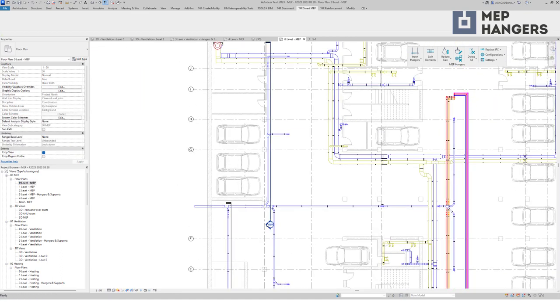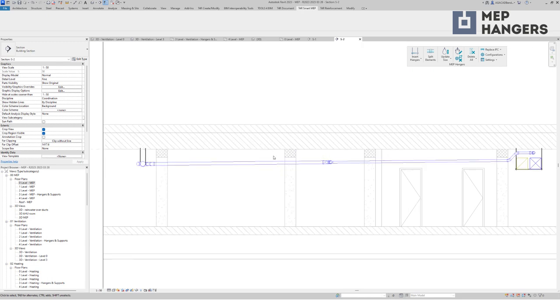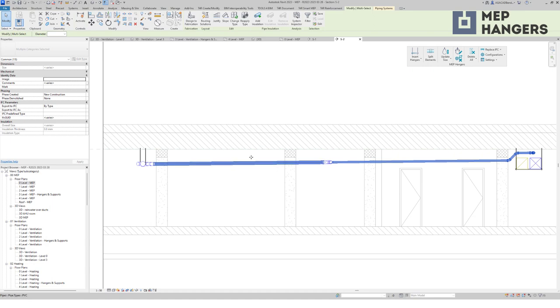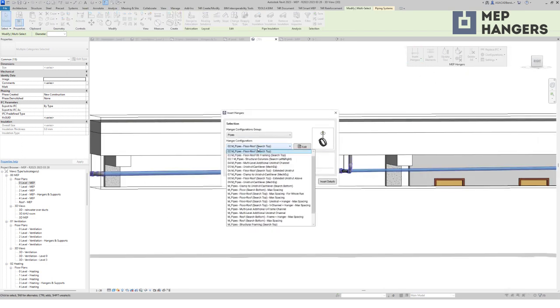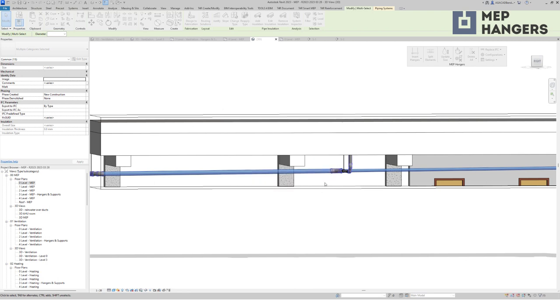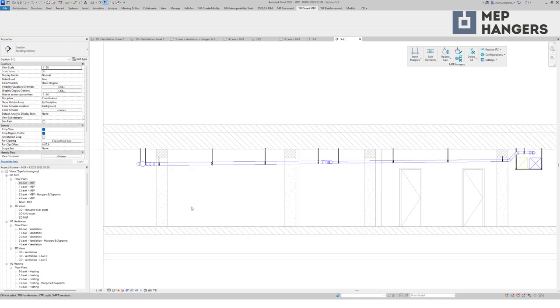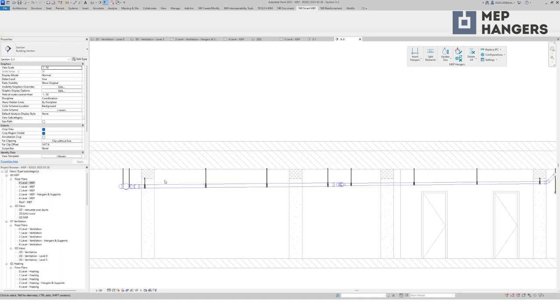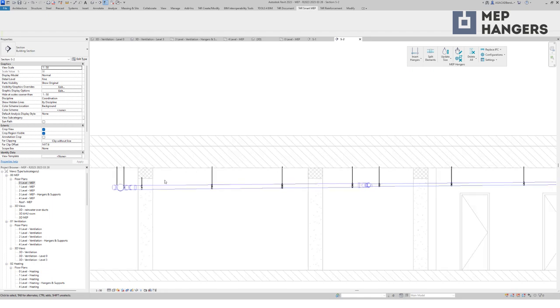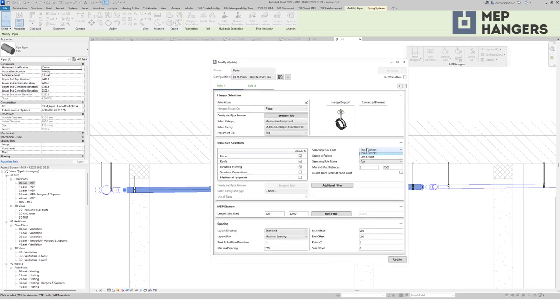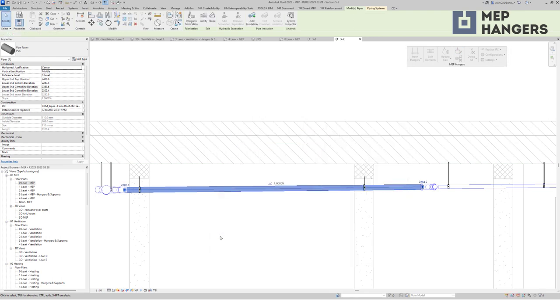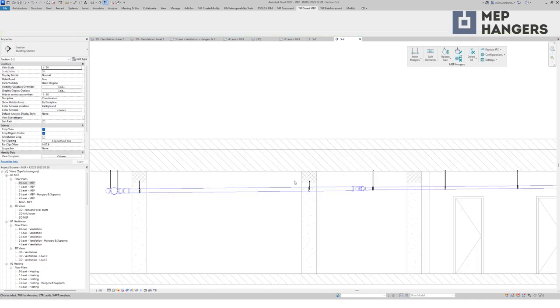Multiple structure categories at once are also supported. For example, here I have a floor above and also some concrete beams running perpendicular to my pipes. I can run a configuration which looks for both floors and structural framing category elements to connect hangers to, and each hanger stops at the first structure it finds. MEP Hangers also has a functionality called virtual intersections — you can find structural elements above or below MEP elements and place hangers exactly there. I will modify my configuration to use virtual intersections, and now I have hangers placed exactly where every beam passes.